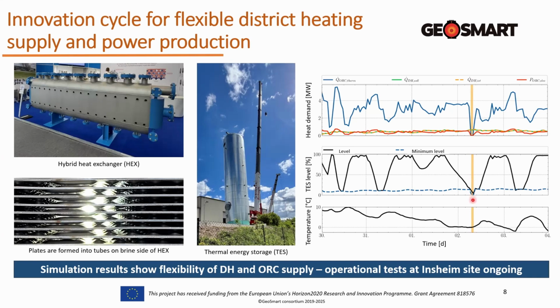So we have to use the thermal energy storage as a redundancy for the district heating. It seems during this simulation that even with the level already 20% discharged, we could still provide energy for at least 2 hours for the district heating. This is usually enough to restart the power plant, so that's a good result.